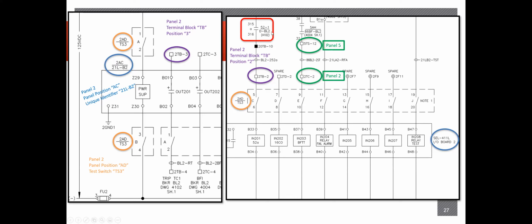So this 52.1, which one is this? I have no idea. So I guess it's supposed to be, oh yeah, it is breaker contact. Sorry, I didn't see the A there. So this is identified as breaker contact, normally open, and it's obviously the primary input for designating whether the breaker is either open or closed in the relay.